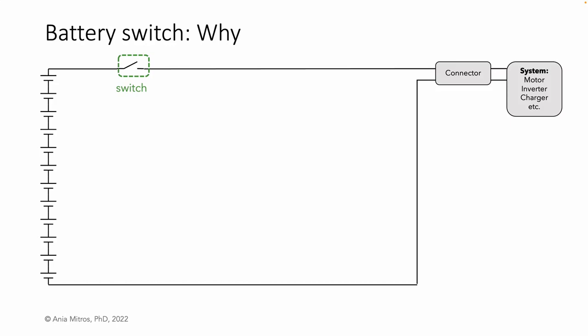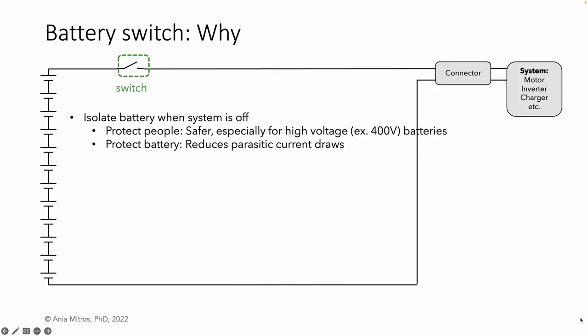This is important for a few reasons. When the system is off, disconnecting the battery is safer, especially for high voltage batteries that may have 400 volts or 800 volts at the terminals. For example, we don't want a mechanic servicing another part of the system to inadvertently short the battery with a metal tool.